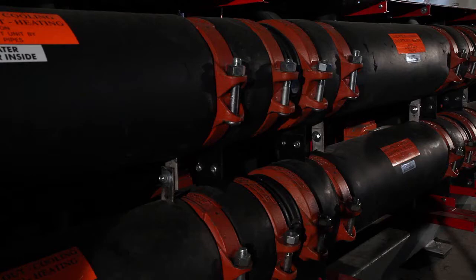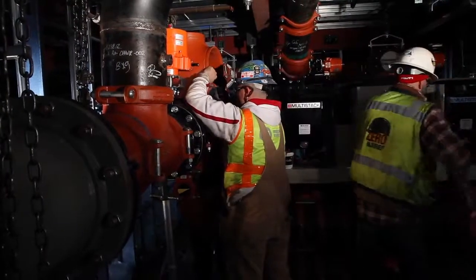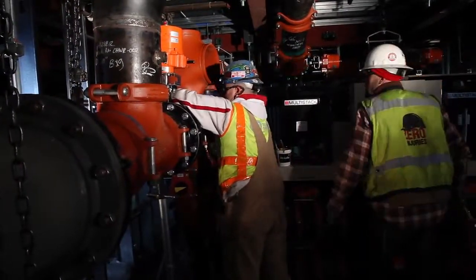Instead of using a cooling tower to reject heat, we're actually rejecting heat to the bay through the use of the heat exchangers. So we pump water out of the bay through a series of mechanical equipment, including a heat exchanger, and then we pump it back to the bay. There's no chemicals used. 8 50-ton water-to-water heat pumps will be responsible for adjusting the water temperature.